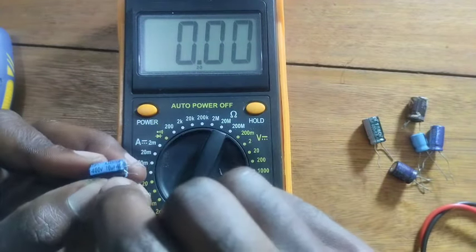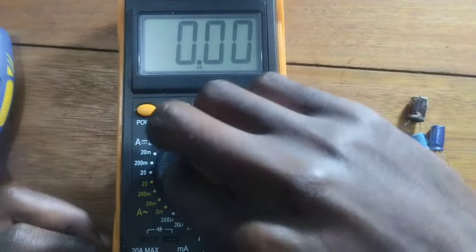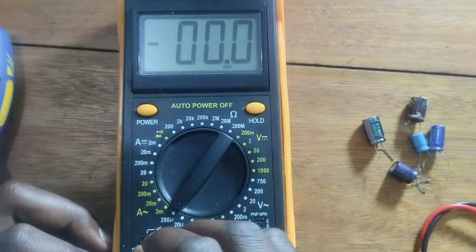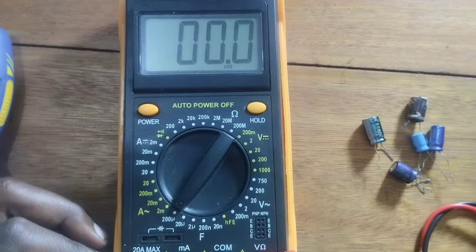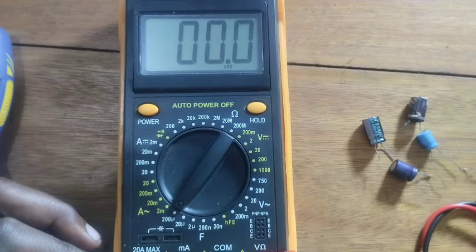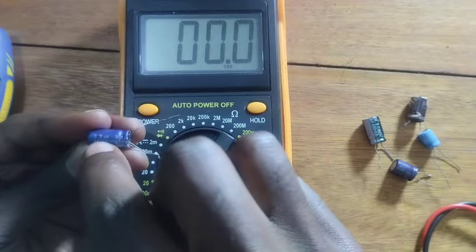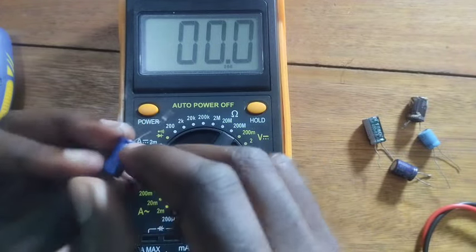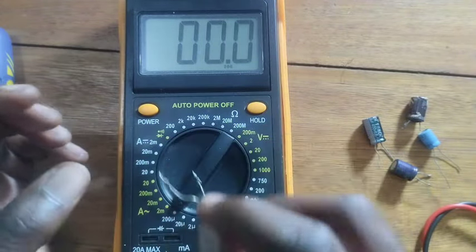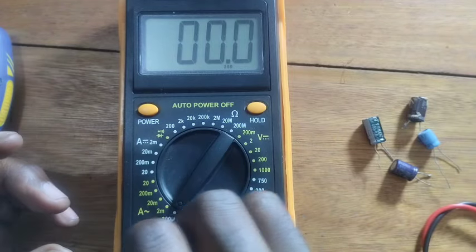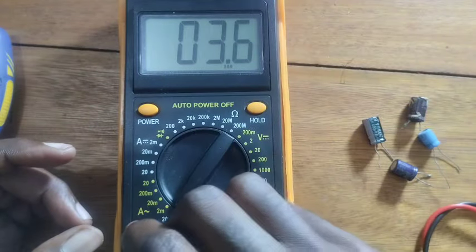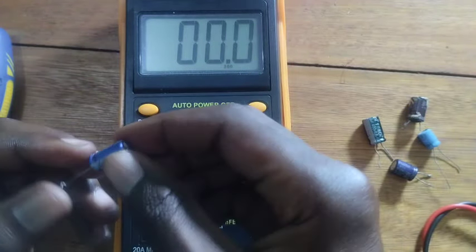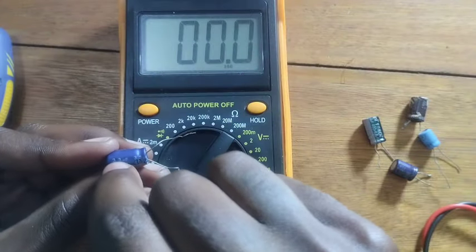This one here is 3.3 microfarads, positive and negative. Press positive, it gives 3.6 microfarads. That means it is still good because it's close to the rated 3.3 microfarads.